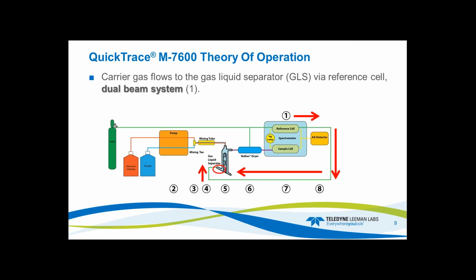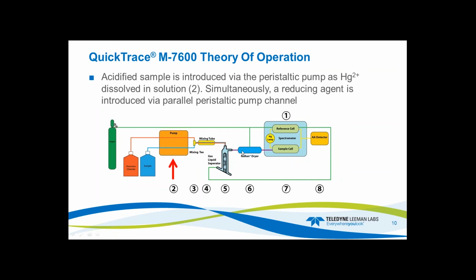So the carrier gas flows to the gas liquid separator through the reference cell. So it's a dual beam system. So here we look on the schematic. That's coming from the gas regulator through the reference cell and then down and over to the gas liquid separator. Then the prepared sample is introduced by a peristaltic pump, and it's got to be Hg2+, so it's dissolved in solution. And at the same time, the reducing agent is introduced by a parallel peristaltic pump channel.